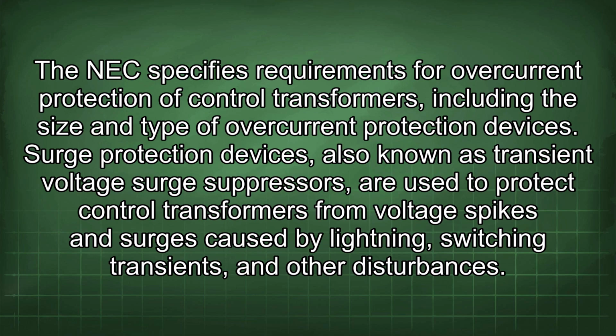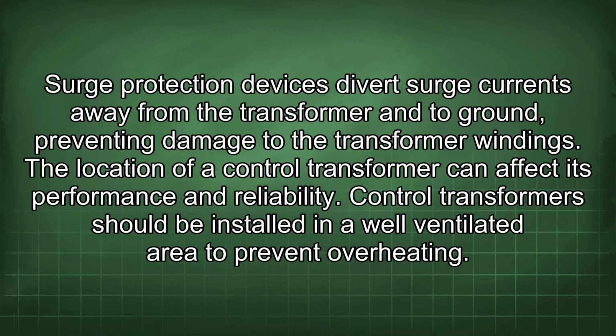Surge protection devices, also known as transient voltage surge suppressors, are used to protect control transformers from voltage spikes and surges caused by lightning, switching transients, and other disturbances. Surge protection devices divert surge currents away from the transformer and to ground, preventing damage to the transformer windings.